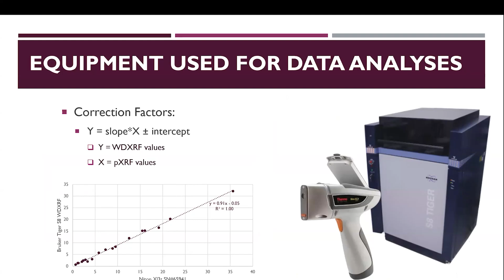The kit has been measured twice using this Niton analyzer, once before the factory calibration that was done in 2024, and once after. The comparisons between the results of this kit before and after factory calibration showed that most elements have similar results to the reference values, and that their concentrations remained almost the same before and after factory calibration, with similar equipment bias of systematic over- or underestimation of certain elements, with very slight modifications sometimes in either precision or accuracy of data after equipment calibration. However, some elements showed better results after equipment calibration, especially phosphorus, an element which, however, is more related to the taphonomic effect and is often of very limited use to us for pottery analysis.